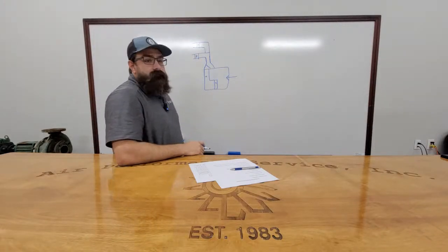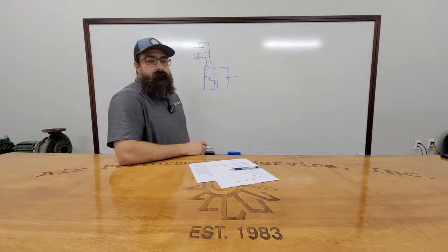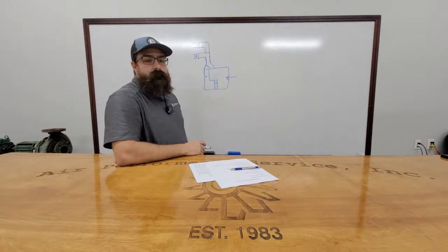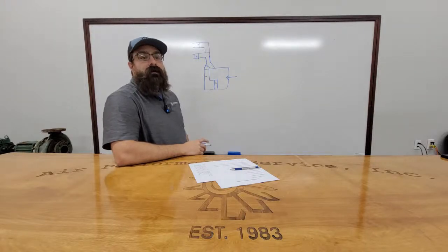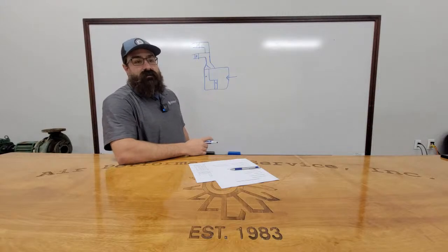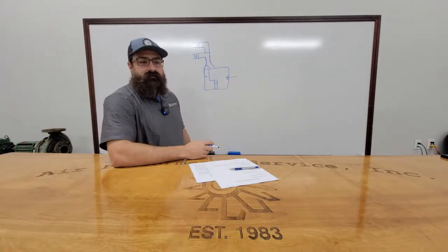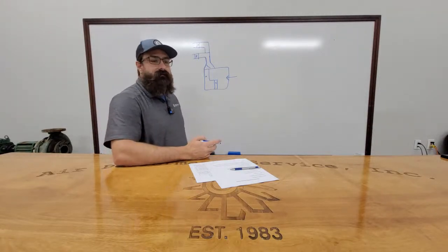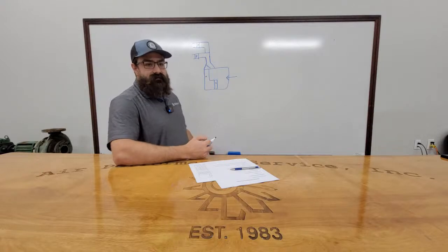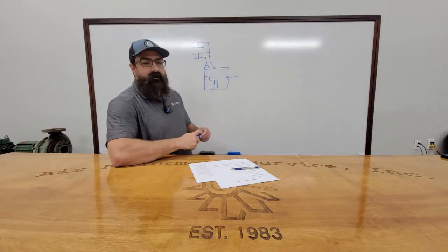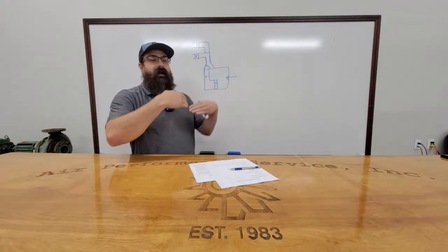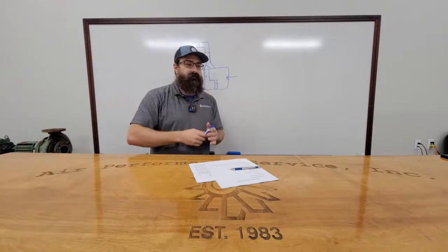I've seen them like that, but I also saw them where you'd have the ductwork where they literally split it in half, you had 90 degree opposed dampers. So that's called a dual duct system. So that's what we call those, dual duct. So in a dual duct system, you have a metering device, which is opposed dampers that one opens, one closes.